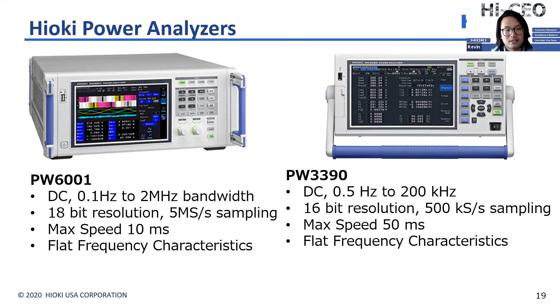Another benefit with the 3390 is that you can connect multiple units together and synchronize up to 8 units. So this will give you 32 channels in total. Now, both of our testers feature a flat response characteristic, and they both have the built-in phase shift function. We'll get into this in a bit, but this allows us to set and correct the phase error of our current sensors. And this will dramatically reduce the measurement error when we're measuring high frequency, low power factor power.